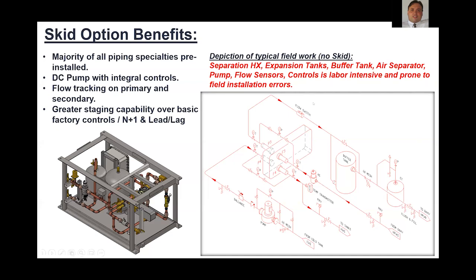This is an isometric depiction of what's required at that brazed plate heat exchanger between the heat pump water heater and the secondary side. You've got buffer tanks, expansion tanks, air separators, pressure relief, temperature sensors, pumps, controls. So that's a lot of field work involved, and that can be a challenge for a lot of the Division 23 or Division 22 type contractors in the plumbing realm. This is outside of the wheelhouse in a lot of cases. It's definitely more suited to Division 23 on the mechanical side, but still, it opens up the potential for more issues, more potential rework in the field.